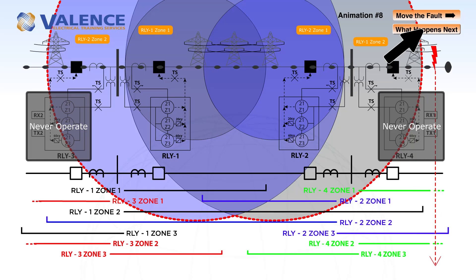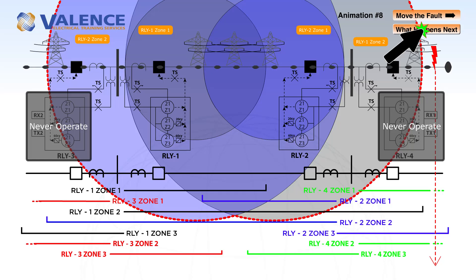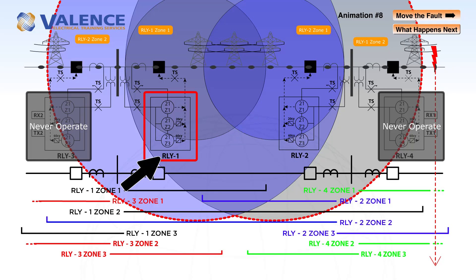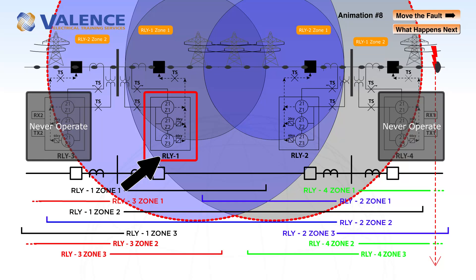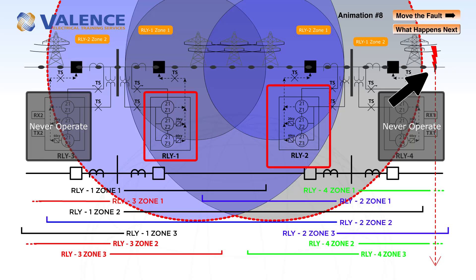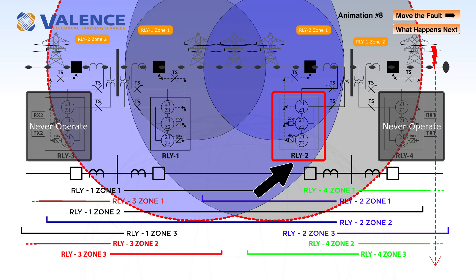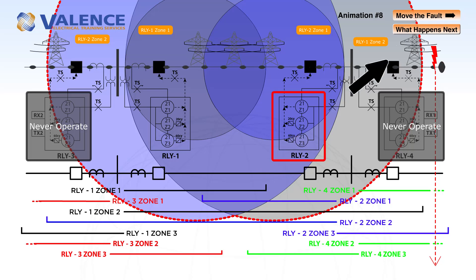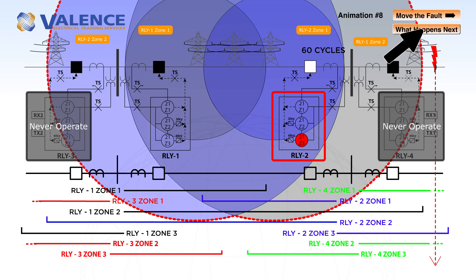If we move the fault outside of relay 1 zone 2, relay 1 is going to ignore that fault completely because it's outside of its zone of protection. But relay 2 is going to detect a zone 3 fault, and it's going to trip in about 60 cycles.